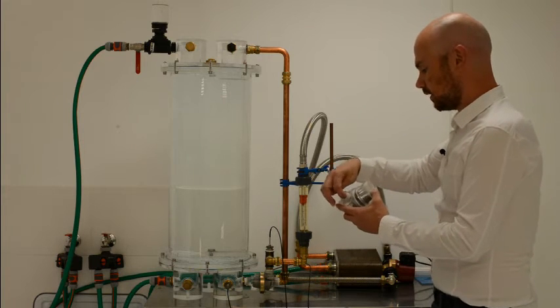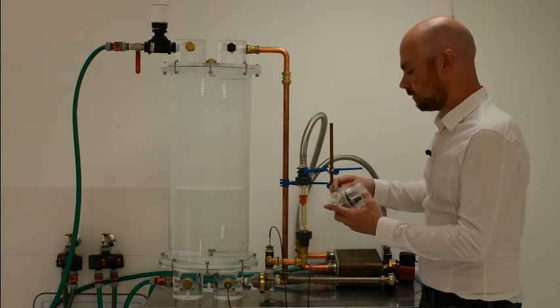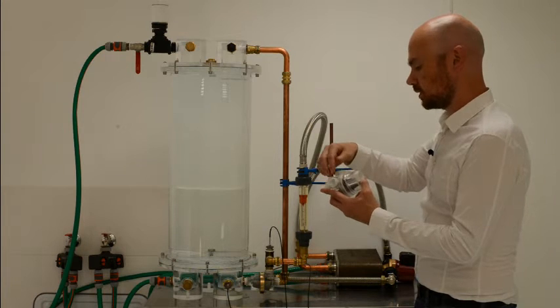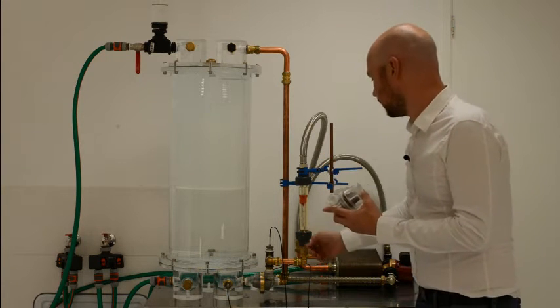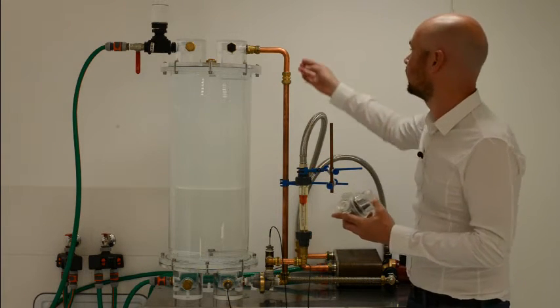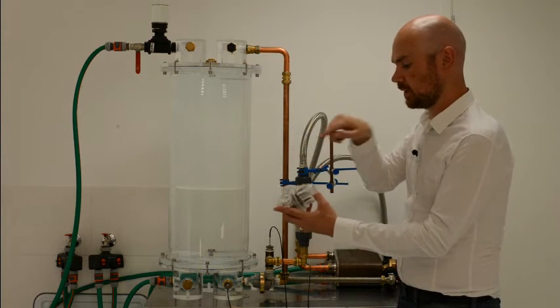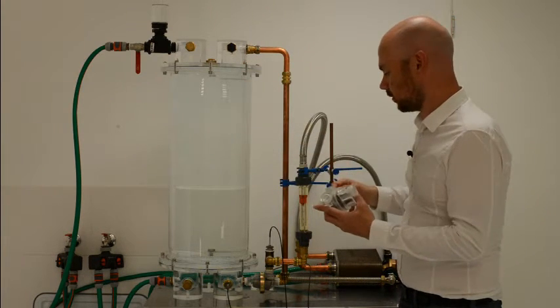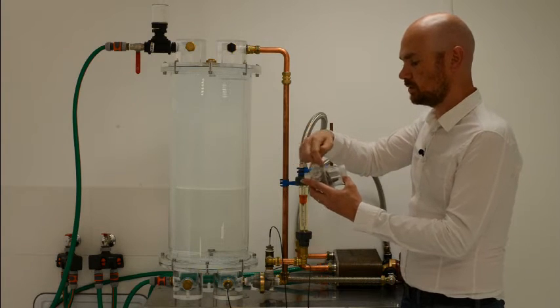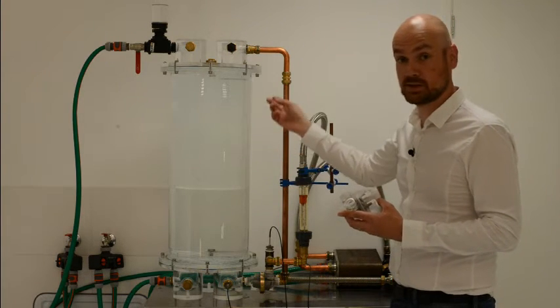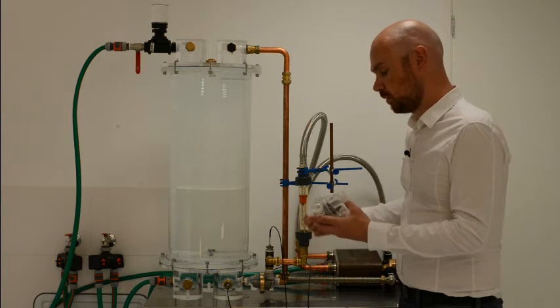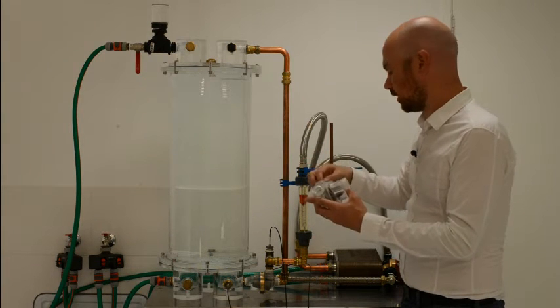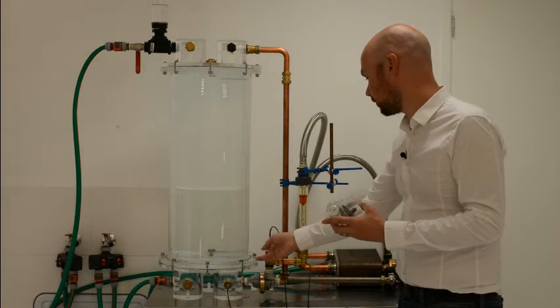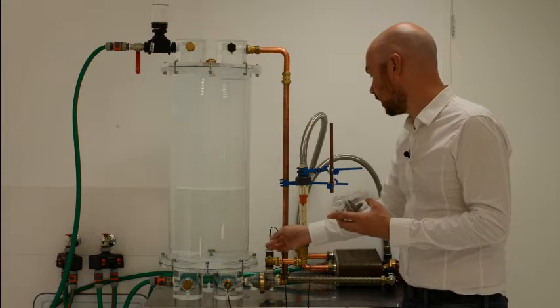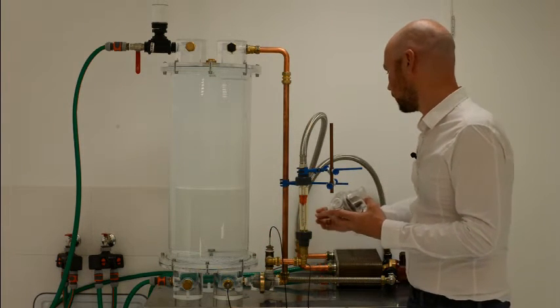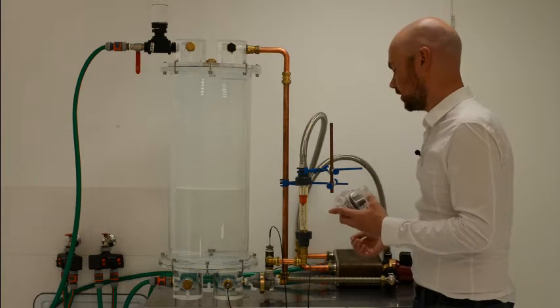Coming into the back of the valve, this is the inlet port here, and the flow can then either go straight back out, because this is essentially a T-section, in which case it goes up and through the tank, and then it comes back into this side of the valve. Or it can go straight into the valve, in which case it bypasses the tank completely. So in both cases the flows come together in the valve and come out through the outlet port coming up here. After that it passes through this flow gauge here and back through the heat exchanger.